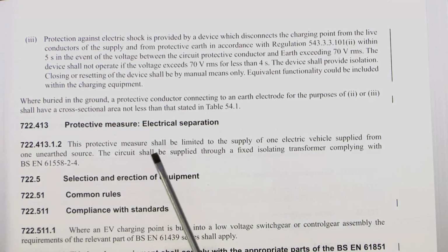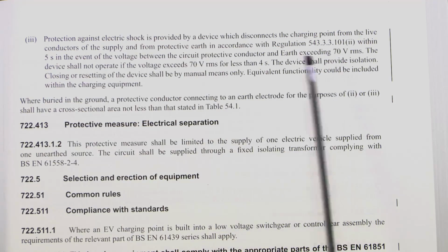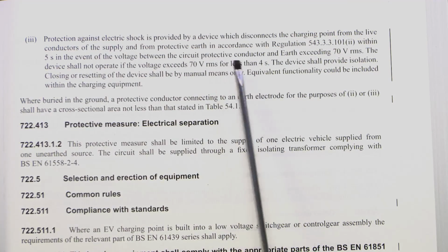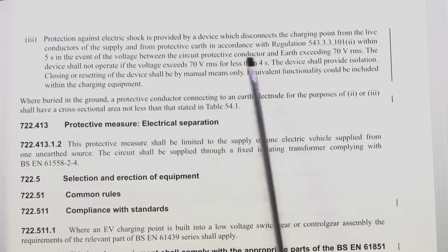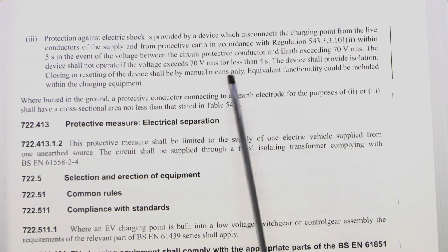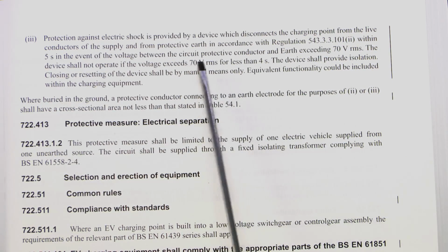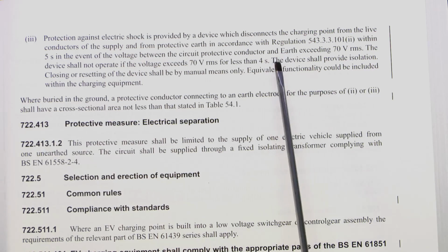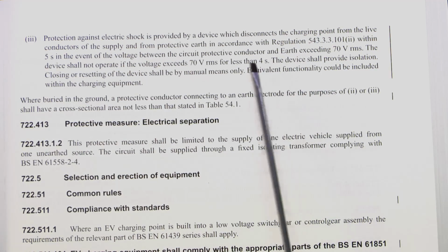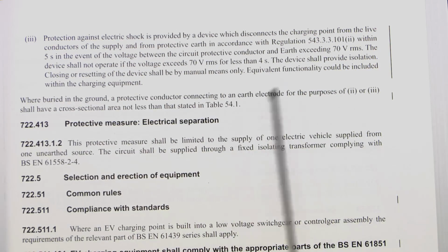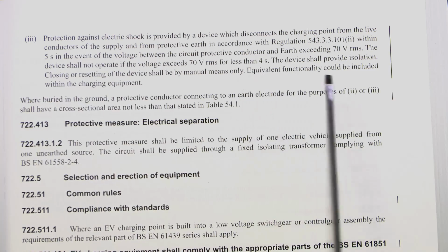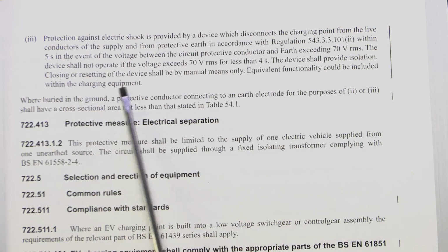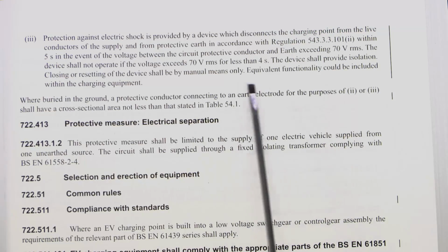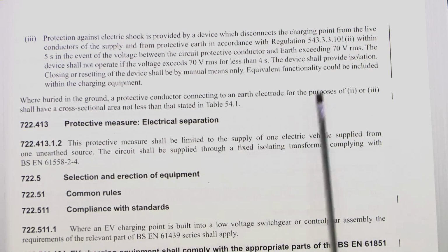So in this particular instance the device would disconnect that protected conductor because it's actually disconnecting it to provide a means of safety, so then you don't have somebody standing outside on the ground holding the charger in their fingers and getting electric shock from the protective conductor. So it seems likely that presumably manufacturers are going to include this thing within the charging equipment itself, but if not, then you would have to of course install a separate device for that purpose.